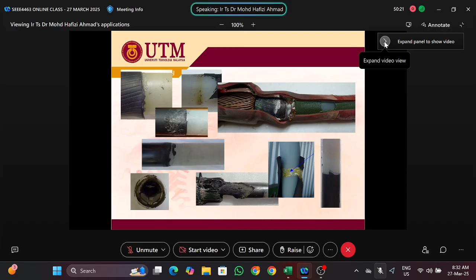So there are some other techniques, basically using capacitive or geometric field grading. This is called a stress cone. They have a deflector, which is used to guide the electric field at this cable fitting point. So when we install cables or terminations to another conductor of the switchgear, the higher electric field will happen at this area. That's why we require another semiconductor material so that it may reduce the electric fields.